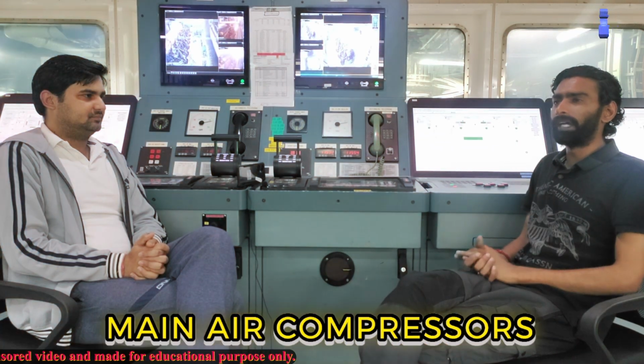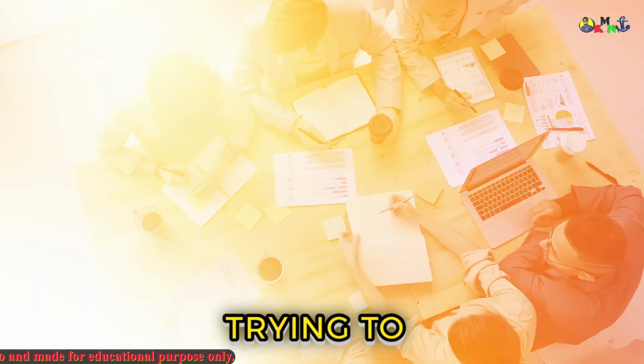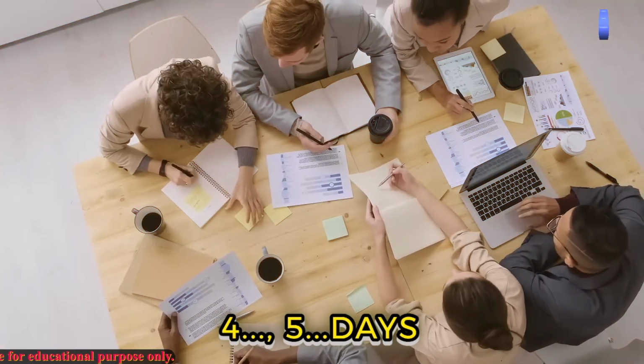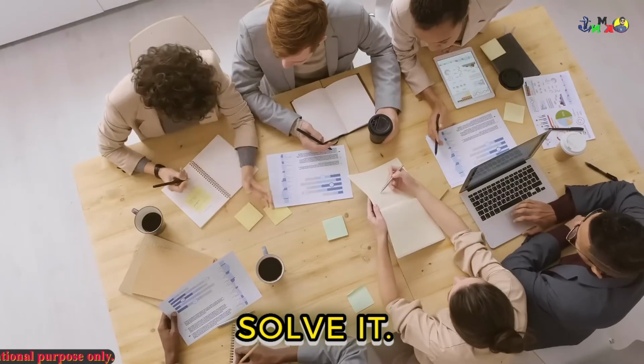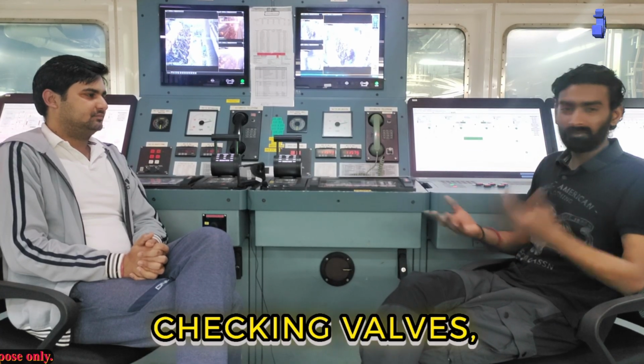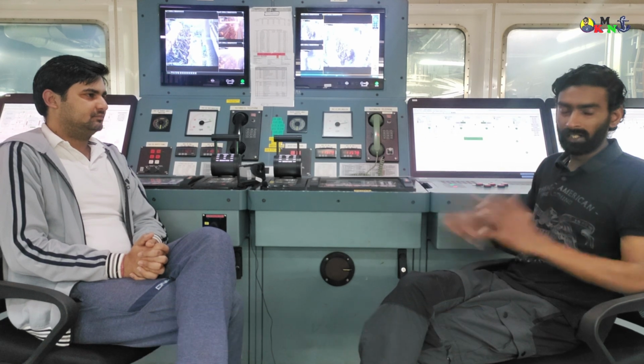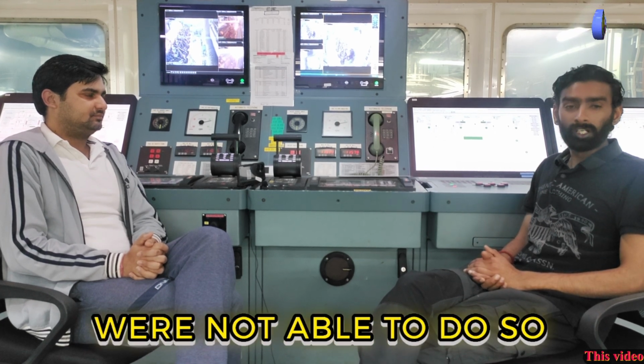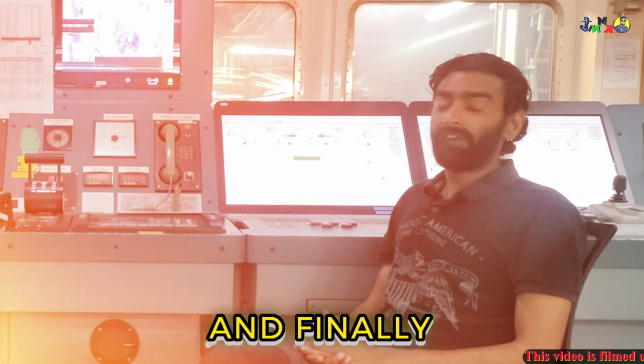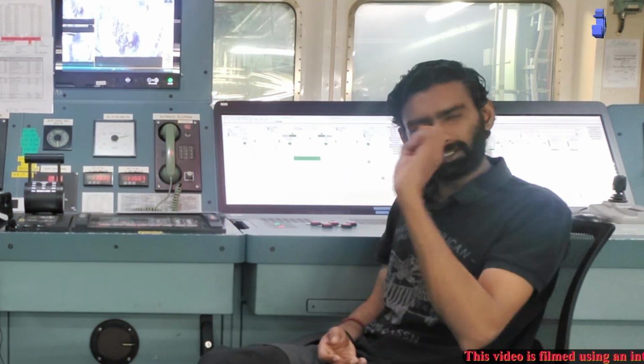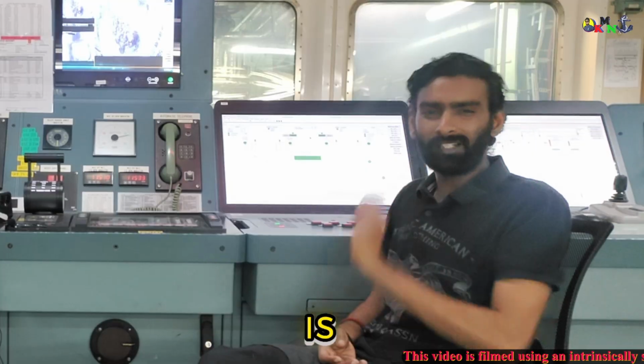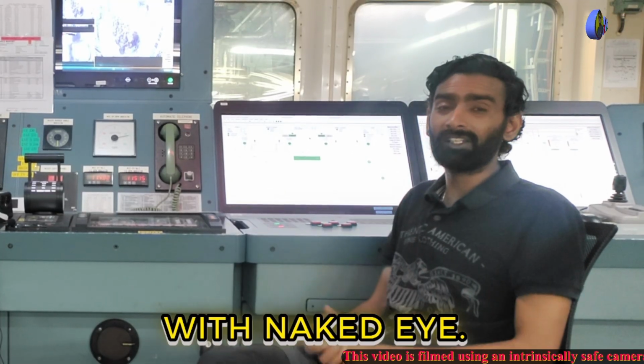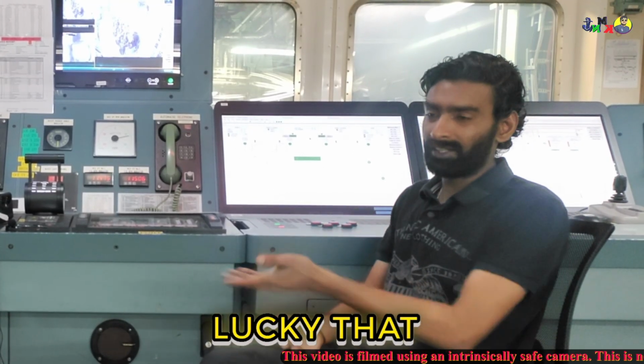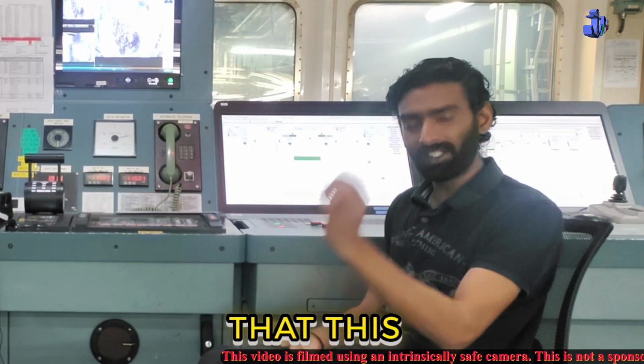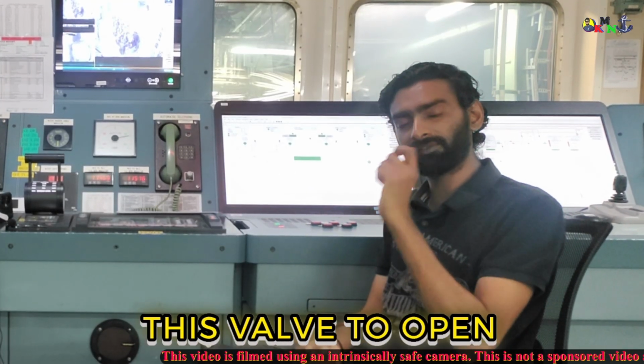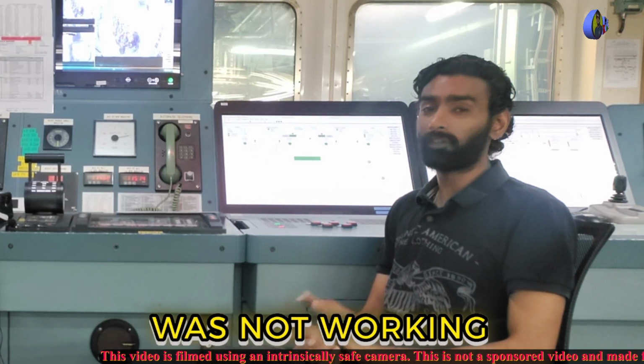We had a problem related to the main air compressors. We were trying to figure it out for 3, 4, 5 days and were not able to solve it. Every time we opened the head, checked valves, opened coolers, but still weren't able to. Finally we overhauled the valves and found a very fine metal piece inside, which you cannot even see with the naked eye. We were just lucky that our hands rubbed on the plate and we found that this slight metal particle was causing the valve to not close properly, and the compressor was not working properly.